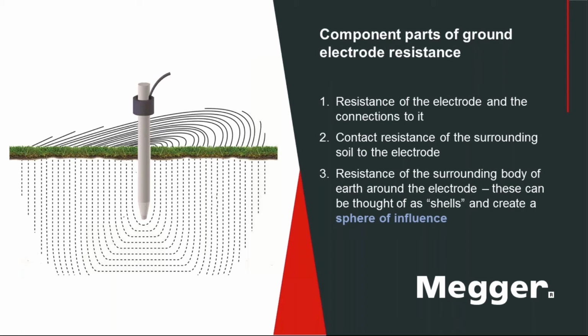So keep it in the back of your mind. If you're in sandy or rocky soil, there is the possibility that contact resistance could be a problem, because there's a lot of air gap in there. It may sound stupid, but if you talk to anybody who's a soil expert, there's actually air around every little grain of sand, and that impedes the flow of current. So sandy soil is bad, rocky soil is bad. You may want to allow for that.